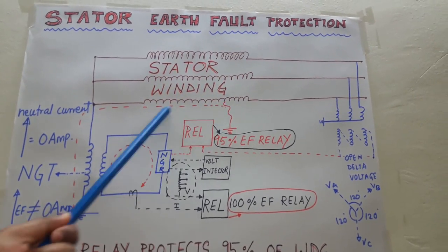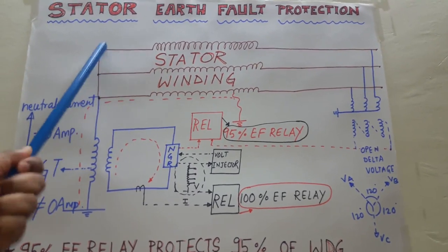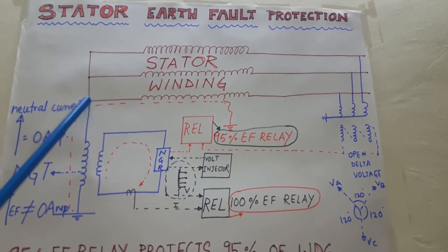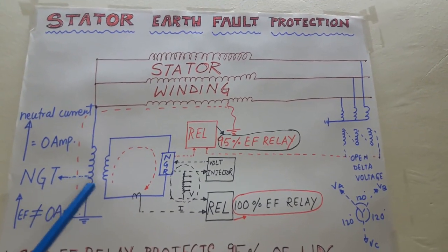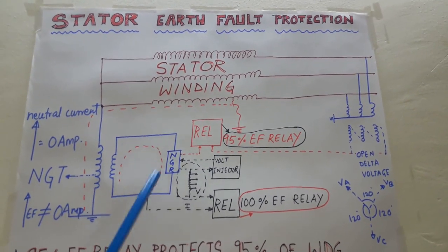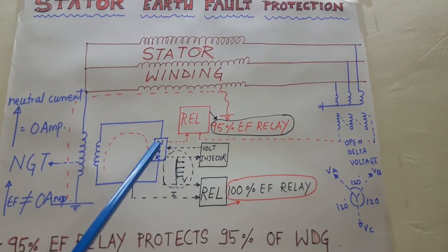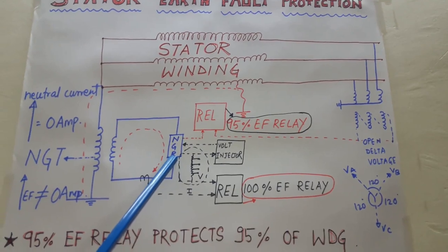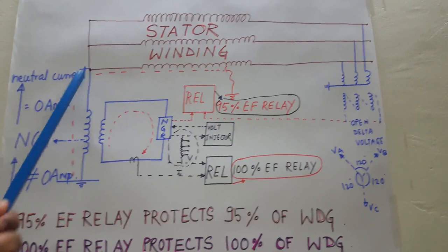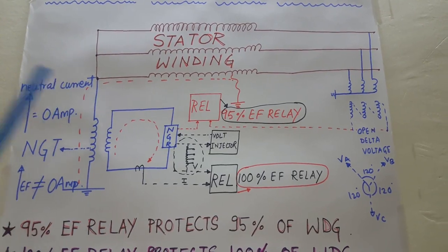This is R phase, Y phase, and B phase. All the three phases are making a star point here which is called the neutral point. From this neutral, you can see the neutral is grounded by the help of a transformer which is called the neutral grounding transformer. Across the secondary side of the NGT, a load resistor is connected which is called the neutral grounding resistor, NGR. During normal condition, there is no current flowing in the primary winding of the transformer and also in the secondary winding — the neutral current is zero.